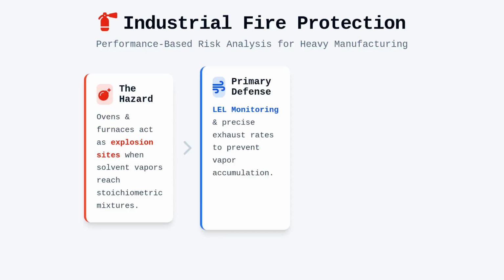Monitoring the lower flammability limit, or LEL, is critical, as any deviation toward the stoichiometric mixture within the oven creates an immediate explosion hazard upon ignition. Ventilation becomes your primary line of defense, requiring precise exhaust rates to maintain vapor concentrations well below the LEL, typically verified by interlock sensors that shut down the heat source if airflows fall below set points.